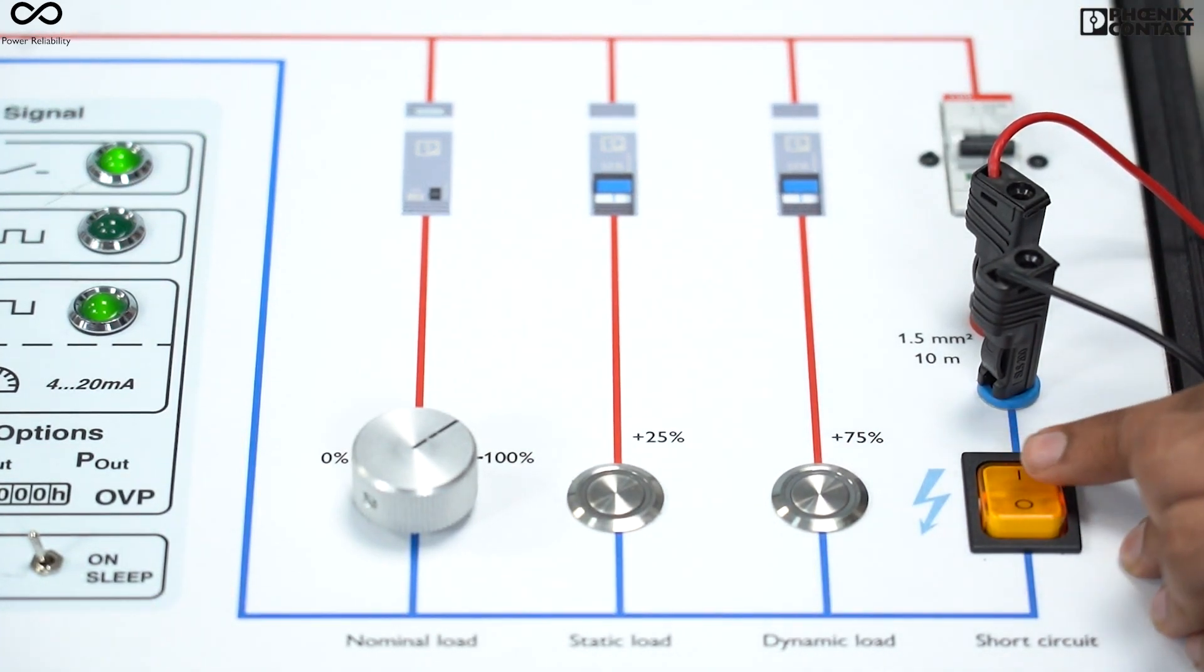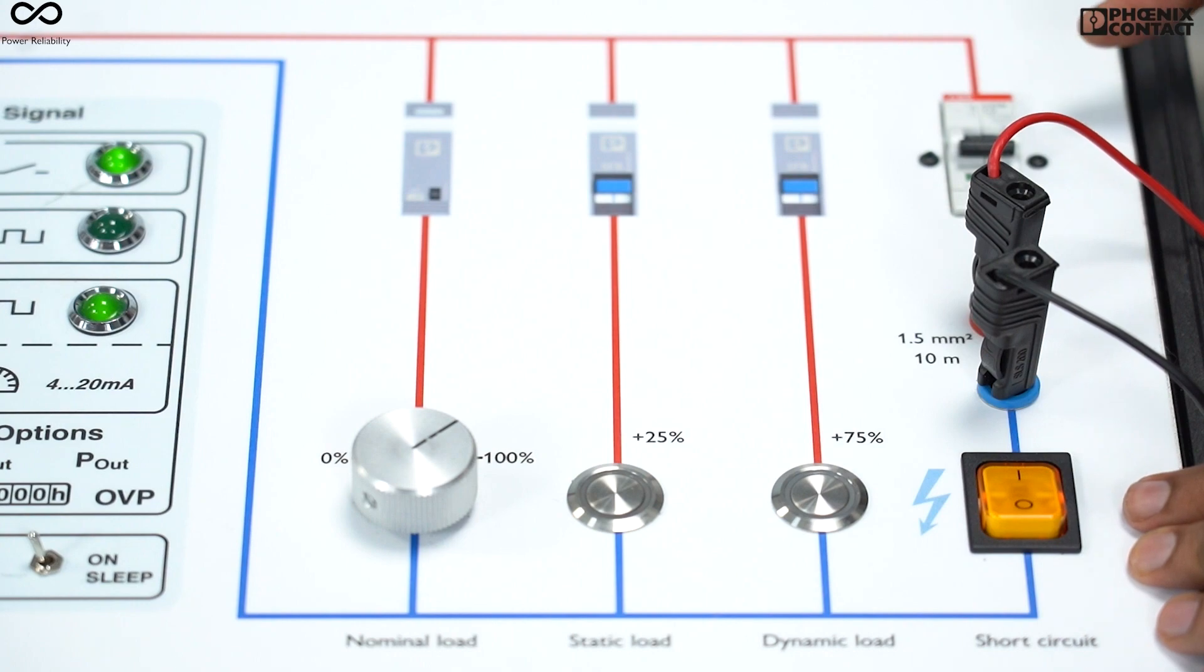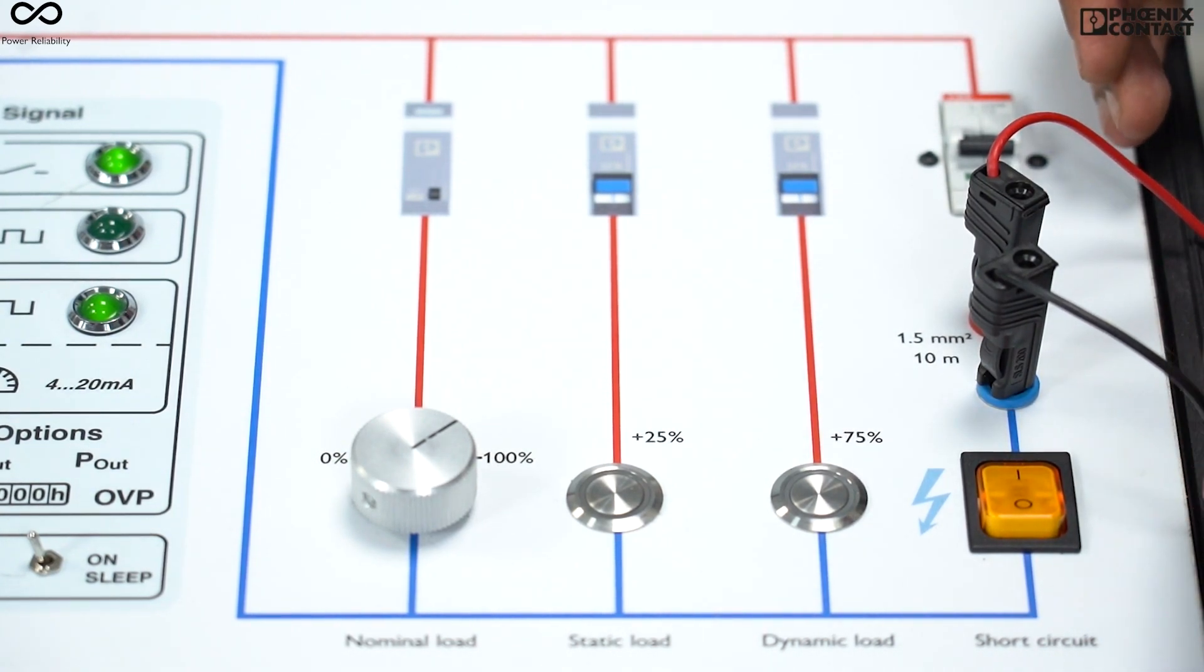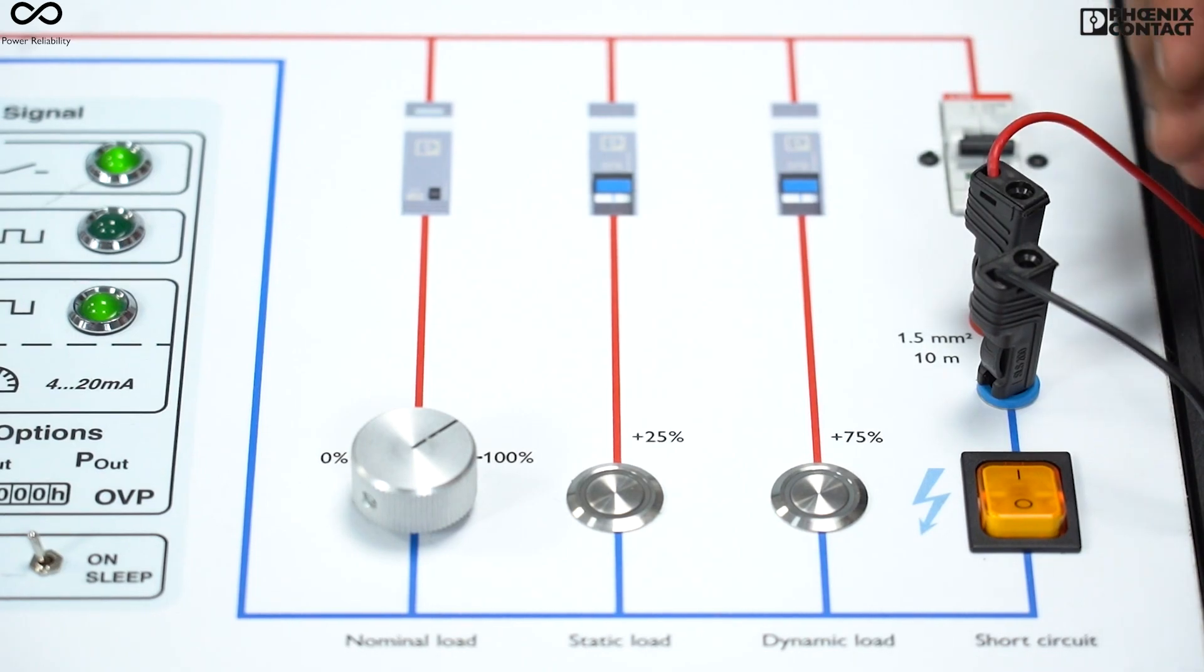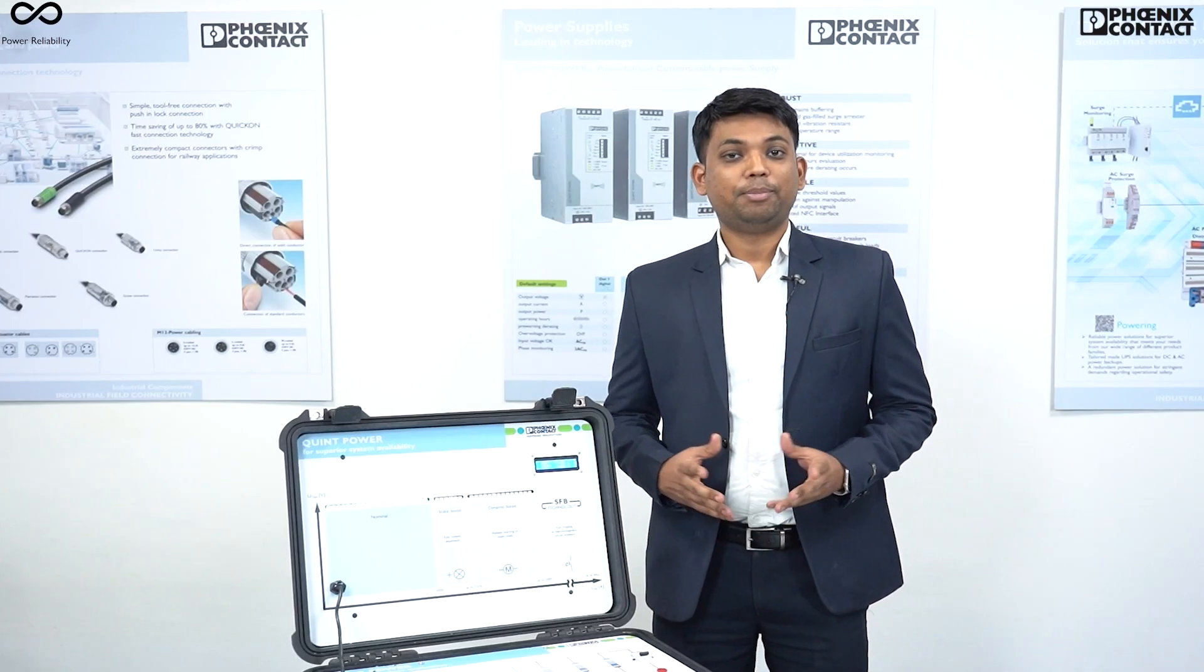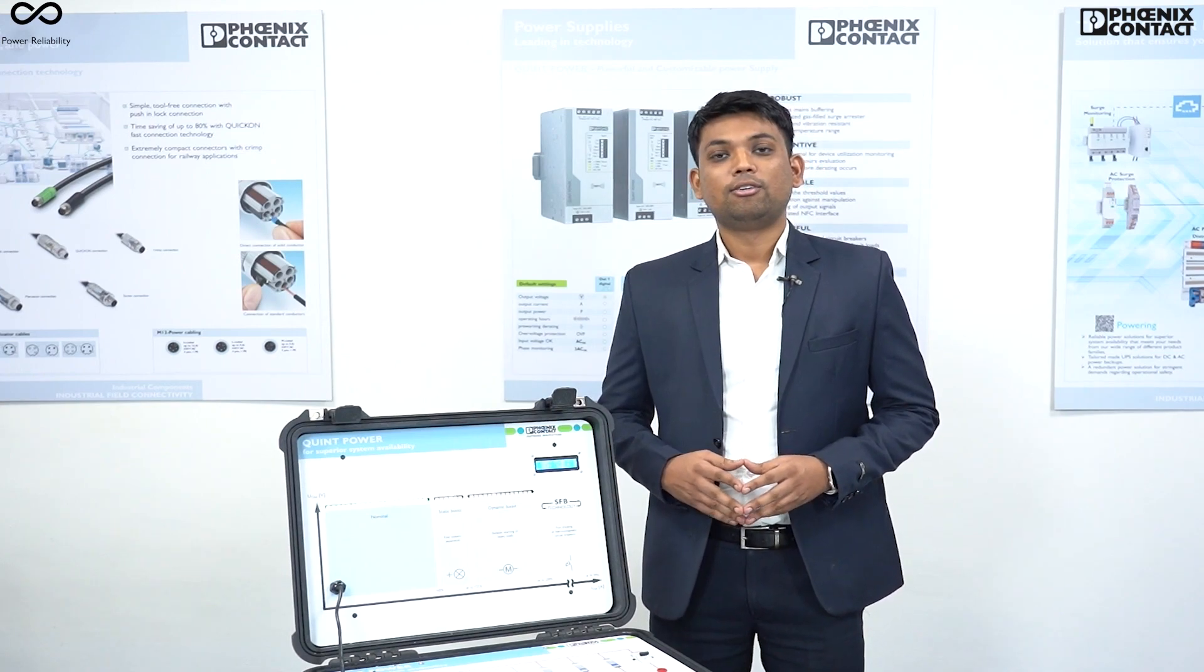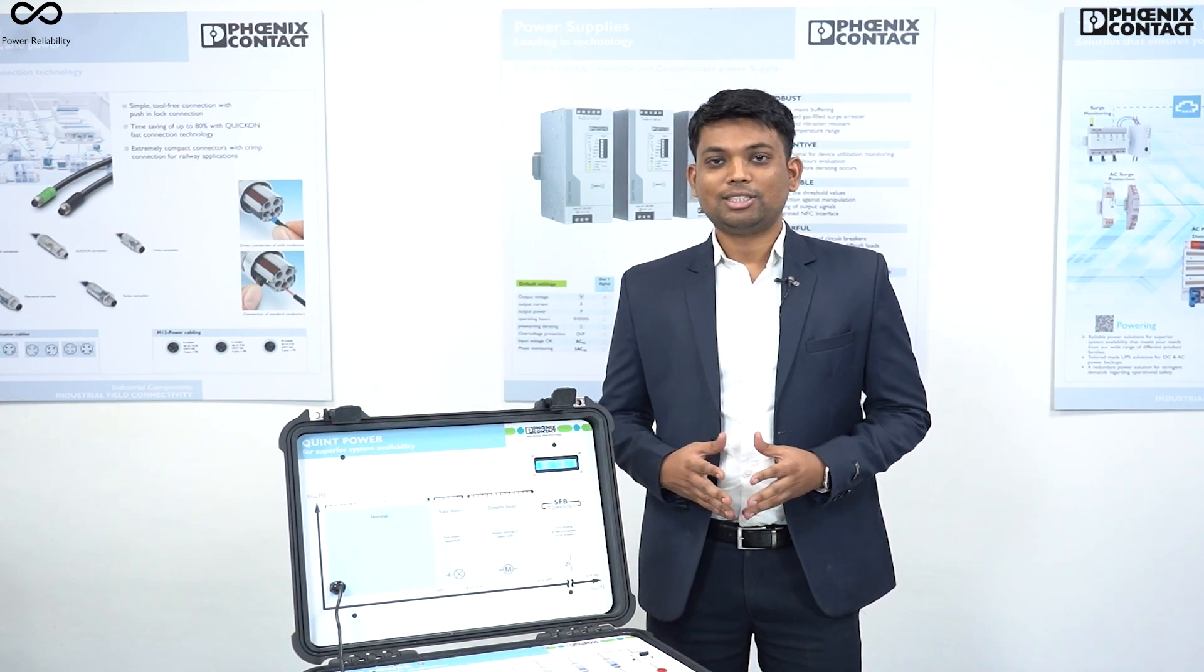So this circuit breaker will trip under 15 milliseconds, and the advantages of having SFB technology is even in your faulty condition, your faulty path will be isolated from the system and rest of the paths will continuously work. So this was a brief demonstration about Quint fourth generation power supply. For more relatable videos, stay connected with us and do visit our website. Thank you.